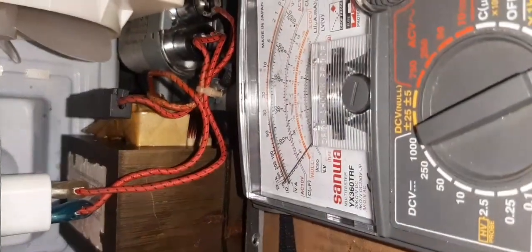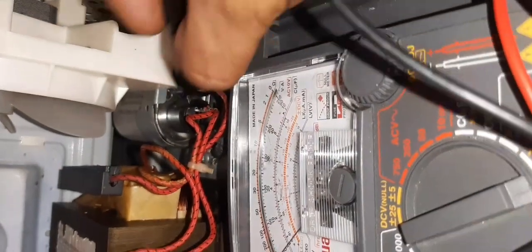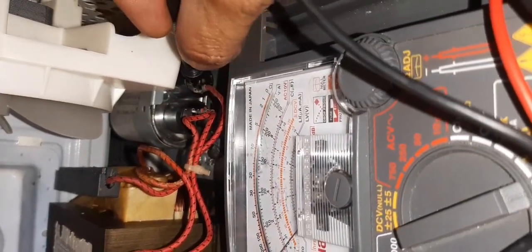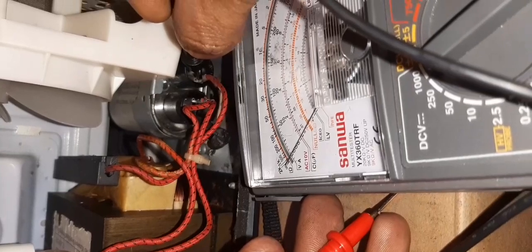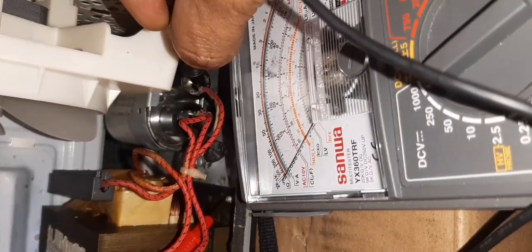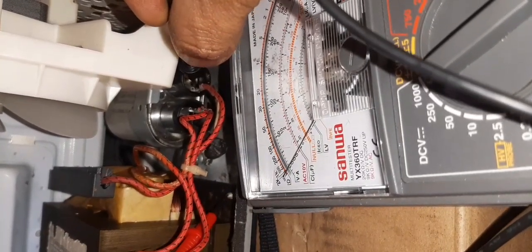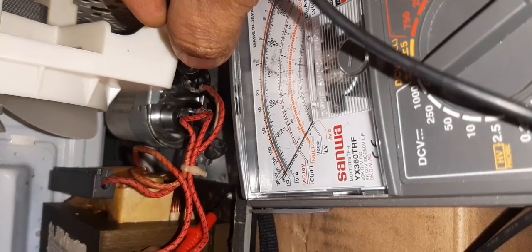Now let's check the third winding of this transformer. This third winding is for the ground connection and has a high voltage. The high voltage of this winding provides between 1800 to 2800 volts. Not much high, but always treat them with utmost respect. If not, it may stop your heart beating, and only God gives a second chance if you make a mistake.